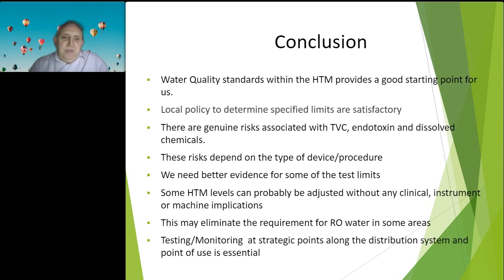So for the water quality standards within the UK, the HTM provides a good starting point. Okay, I would recommend that people use local policies to determine the specified limits as satisfactory. There are genuine risks associated with TVCs, endotoxins, and dissolved chemicals, okay? But the risk depends on the type of the device, the type of the procedure. Do we need better evidence for some of the test limits? Well, yes, like everything else, it's got to be an evidence-based interpretation.